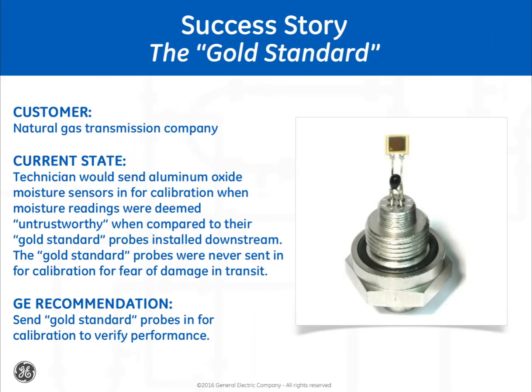There is no more compelling way to describe the benefits of regular calibrations than actual customer experiences. This customer story comes from personal experience when I was an applications engineer. A natural gas transmission company would send in aluminum oxide moisture sensors for calibration only when the moisture readings were deemed untrustworthy. Readings from these sensors were often compared to a standard sensor installed downstream.